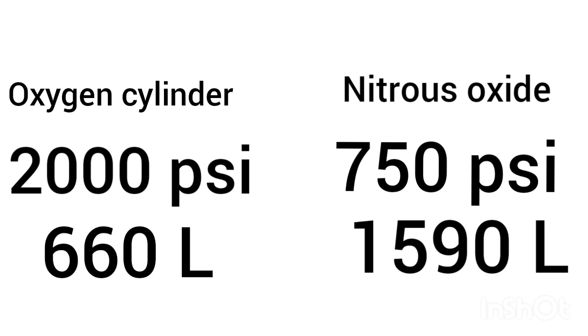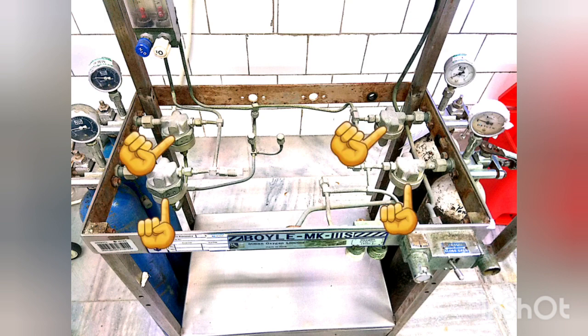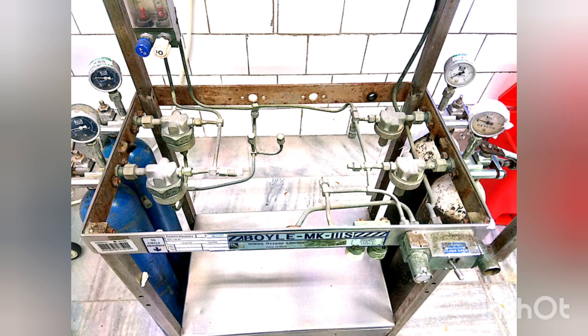After the gas cylinders, the next important feature of the Boyle's machine is the pressure reducing valves. These reduce the high pressure of the gas cylinders — 2,000 psi in case of oxygen cylinders and 750 psi in case of the nitrous oxide cylinders — into 45 to 47 psi.